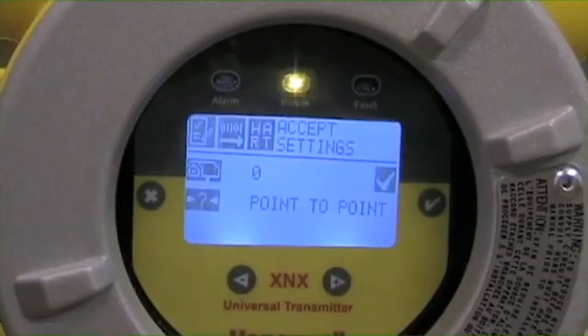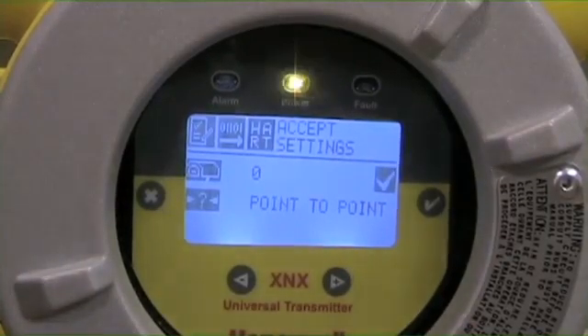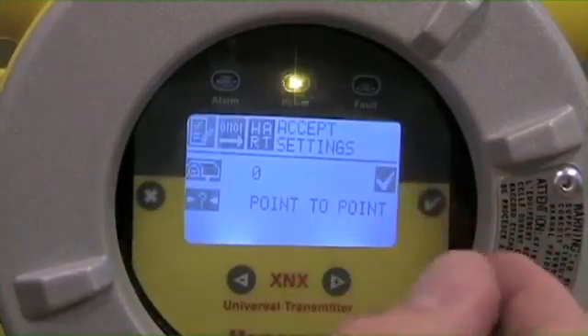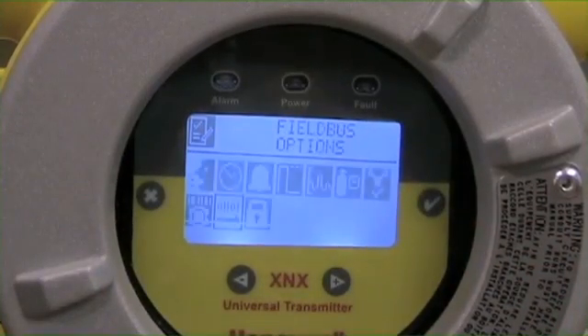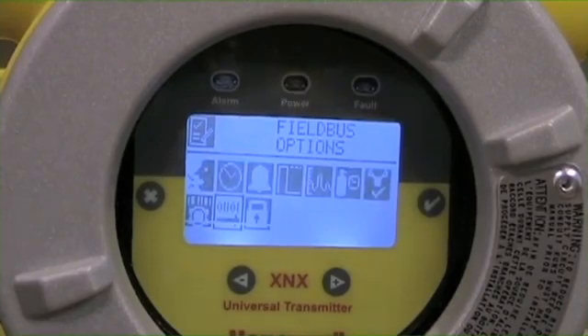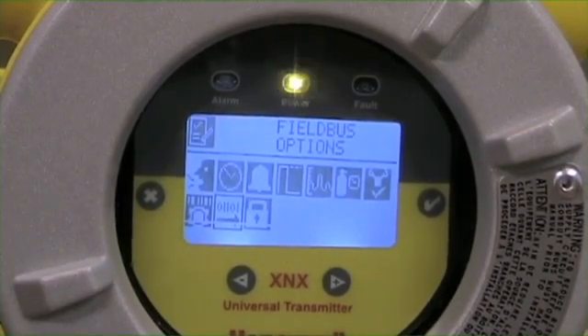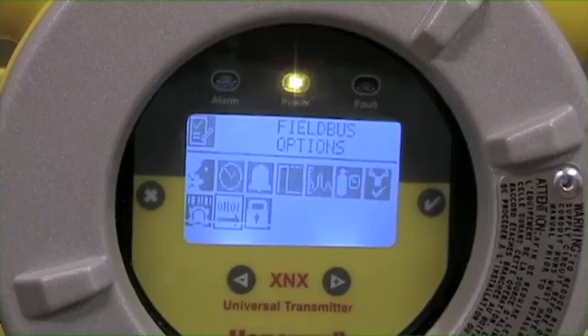In this case, I want to accept address 0 with a point-to-point configuration. I need to move over here to my check mark, engage it, and now it's accepted those settings. It's that simple. We've now set our address in a point-to-point HART communication line.